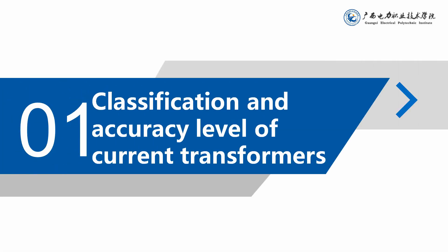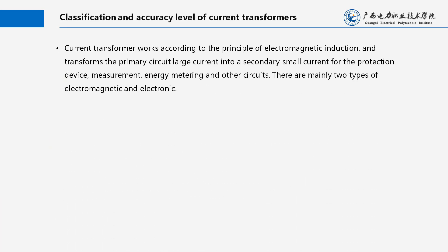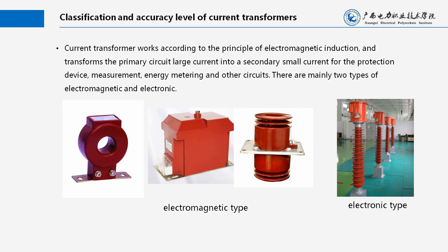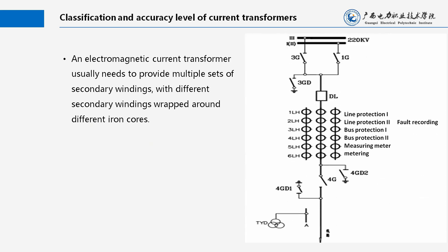Classification and Accuracy Level of Current Transformers. A current transformer works according to the principle of electromagnetic induction and transforms the primary circuit large current into a secondary small current for the protection device, measurement, energy metering and other circuits. There are mainly two types: electromagnetic and electronic. An electromagnetic current transformer usually needs to provide multiple sets of secondary windings, with different secondary windings wrapped around different iron cores.